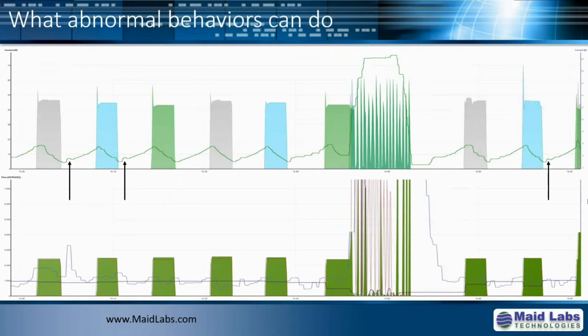And if you look at the 2/3, you can see that the pumps, by the way, on the top part of the graph, these are a pump run time and current. You can see at some point that they just start and stop all the time. These were 3 pumps starting and stopping every 8 seconds for many hours.